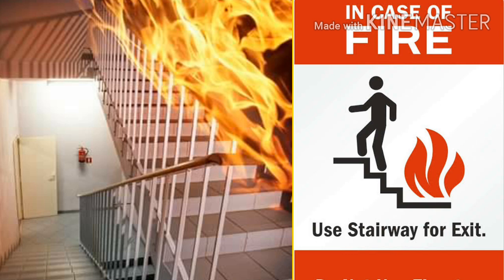And the staircases. Every fire system staircase is very important. For all the staircase provisions, we followed Indian Standard 1644 1988 in deciding the number and location of the staircases in hotels. And illumination of the exits and emergency power. Illumination of exits shall be provided through emergency power supply derived from a diesel generator or by self-contained emergency lights.